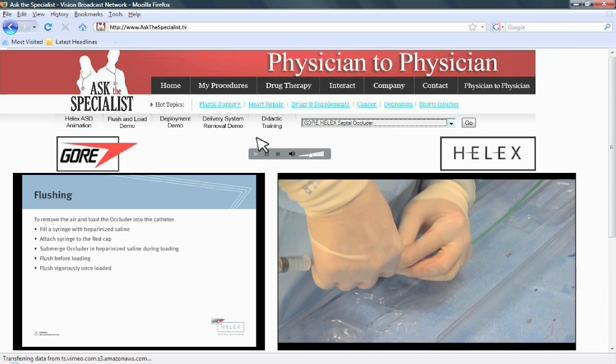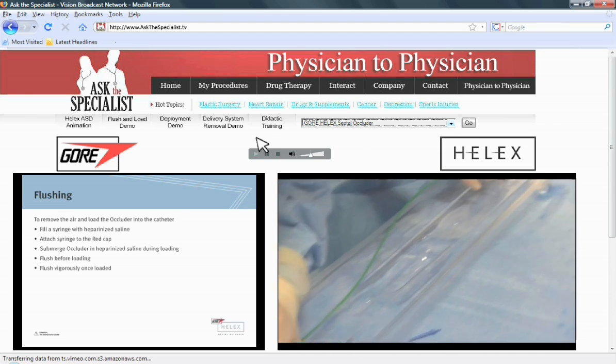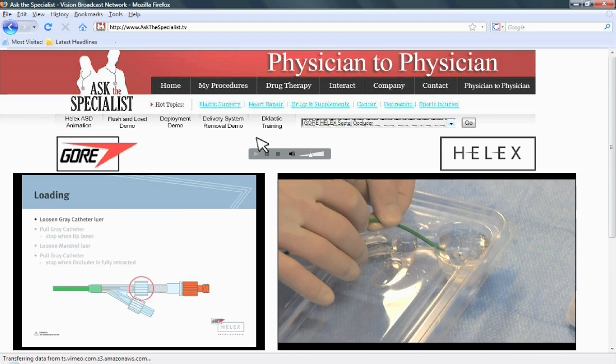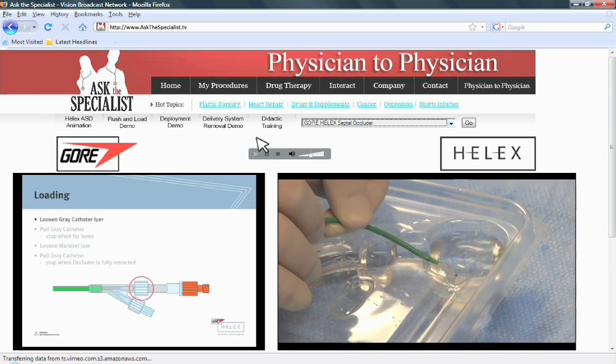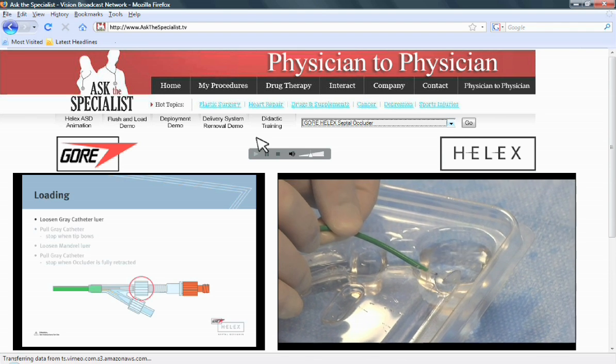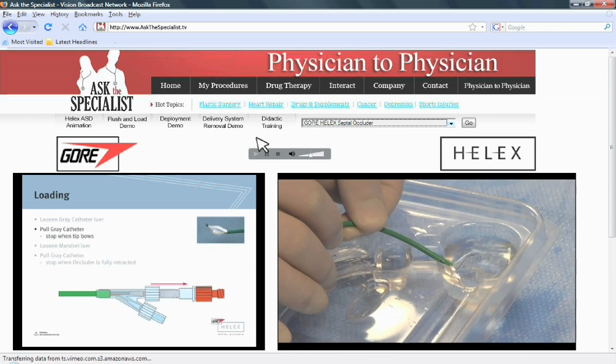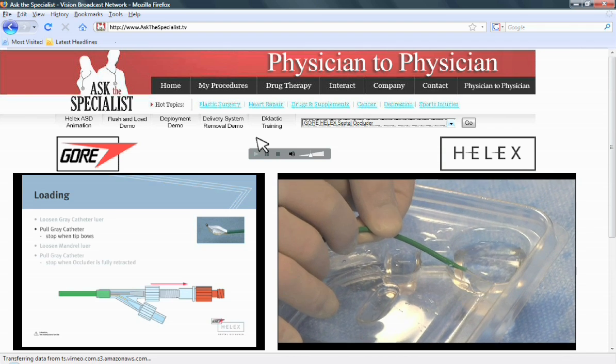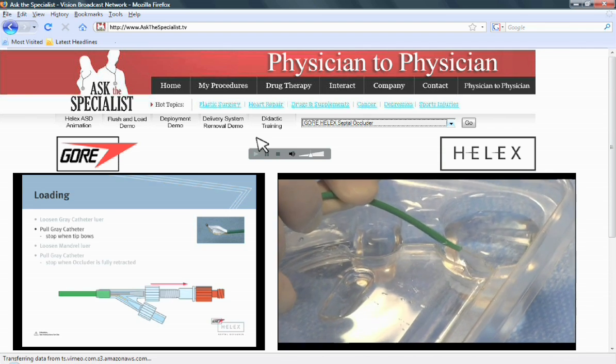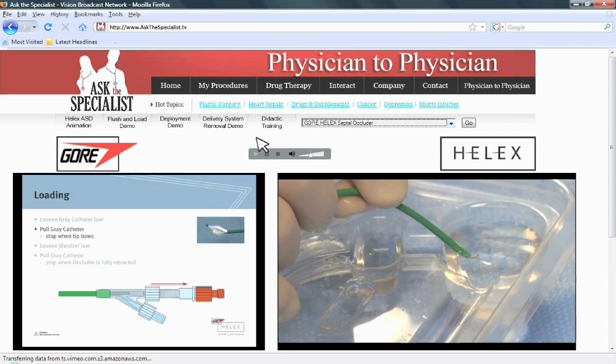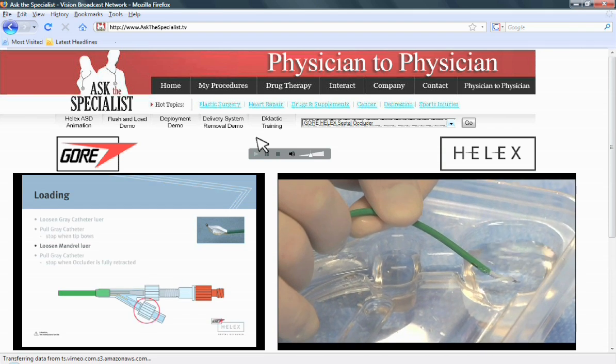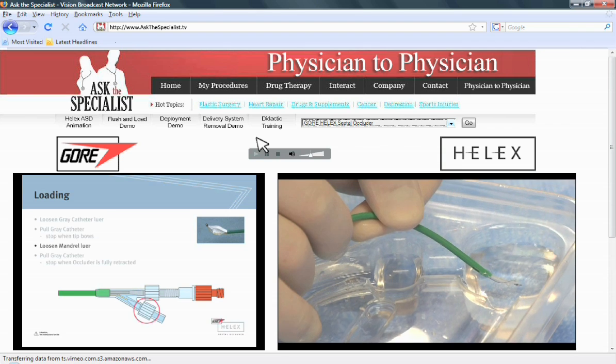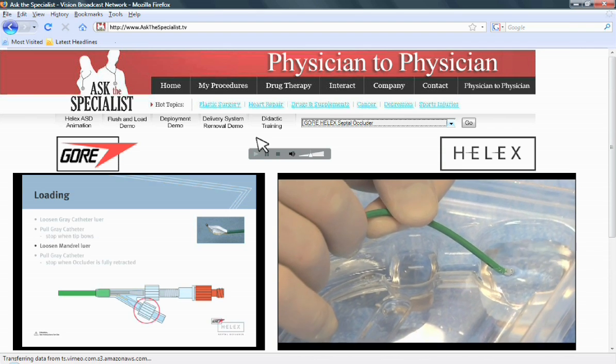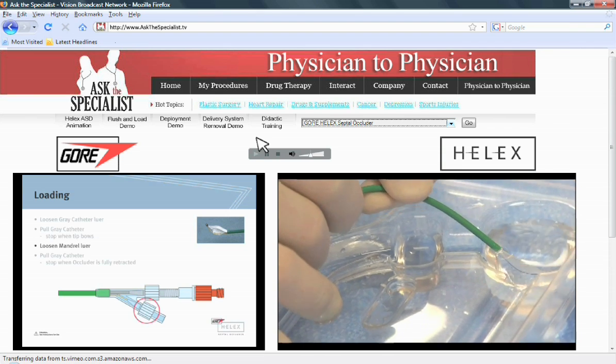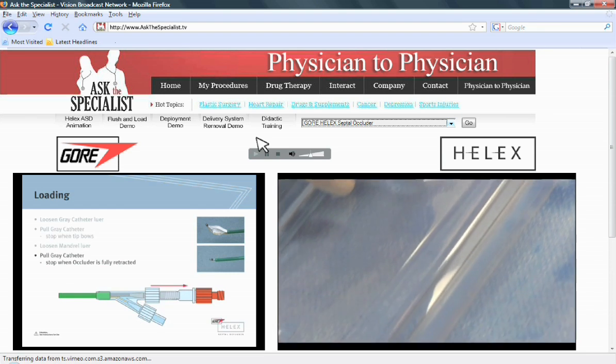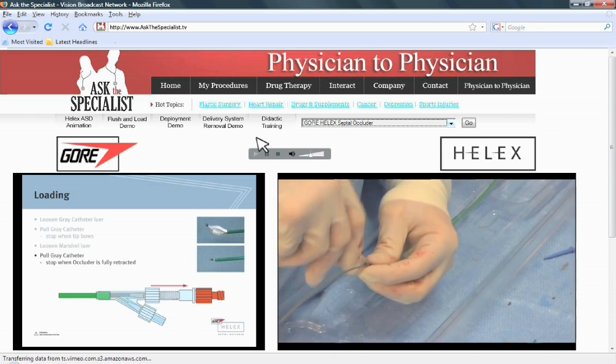So now we're retracting the right disc in, and it's basically, again, a long nitinol wire that's covered with Gore material, EPTFE. Excellent. Get a little bend in the tip and loosen this up and then pull it back in completely. No, we need a little more of that. Push it out with the gray. Push the gray out to lock the mandrel down. Okay. Push the gray out. There you go, lock the mandrel. Just pull back, get a little more of a bend. There you go. Okay.